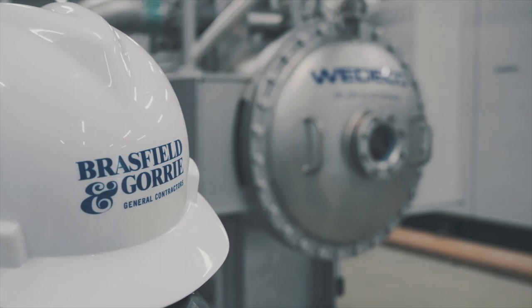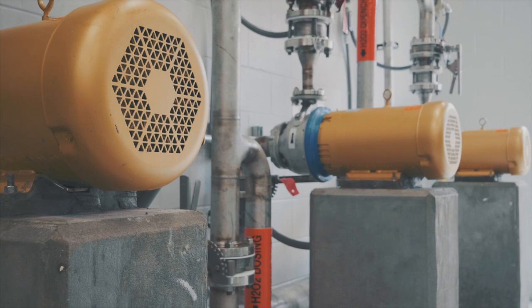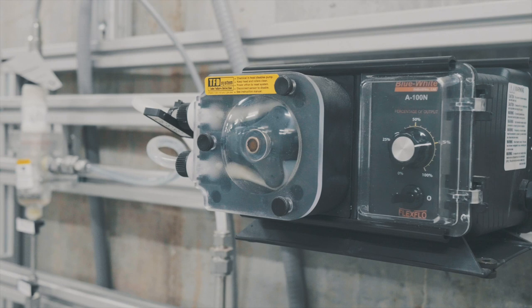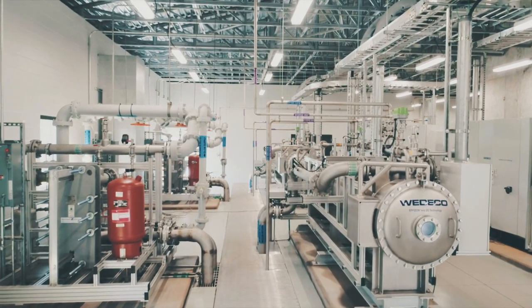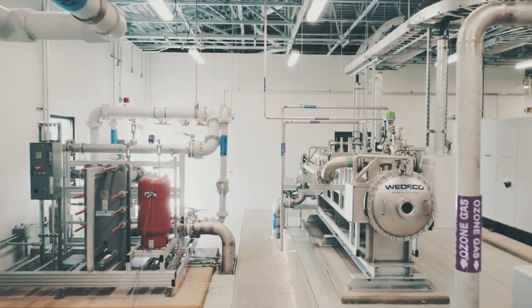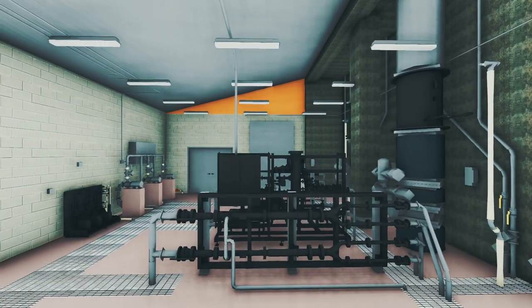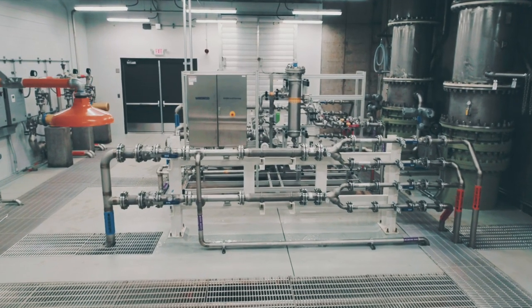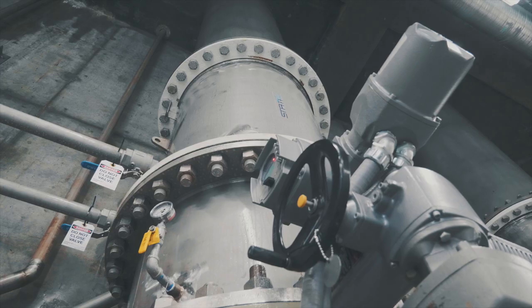After a rigorous evaluation of options, the implementation of an advanced oxidation process was found to be optimal. GMC then recommended an ozone and hydrogen peroxide treatment process. The design of this system began shortly thereafter to provide Anderson Regional the ability to feed ozone alone or augment with hydrogen peroxide to increase performance. Ozone is introduced as a pre-treatment step prior to the flash mixers and pre-oxidizes compounds prior to entering the existing treatment process. The ozone system was designed for two 1,000 pound per day generators with a future generator to provide the ability to feed four milligrams per liter of ozone.